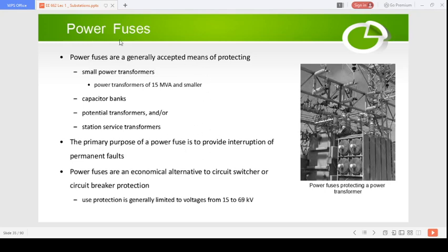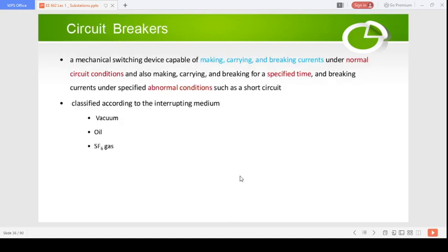The purpose of these power fuses is to provide interruption of a permanent fault. If a permanent fault happens in the system, then you need to disconnect the system from the fault. In order to do that, you can use these power fuses. These power fuses are an economical alternative to a circuit switcher or a circuit breaker. So instead of a circuit breaker, you can use power fuses for low power devices like low power transformers and capacitor banks, as an economical solution. Their use is generally limited to voltages from 15 to 69 kV. So this is the voltage range typically where you can use power fuses. If the voltage is higher, then you have to go for the alternative.